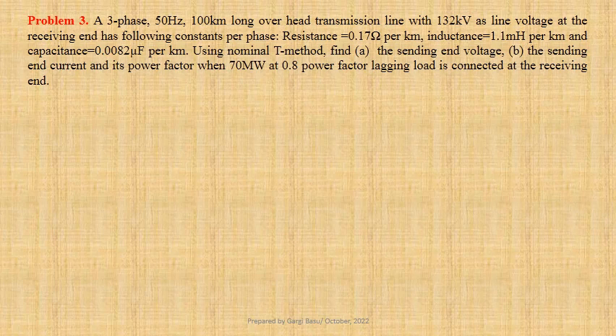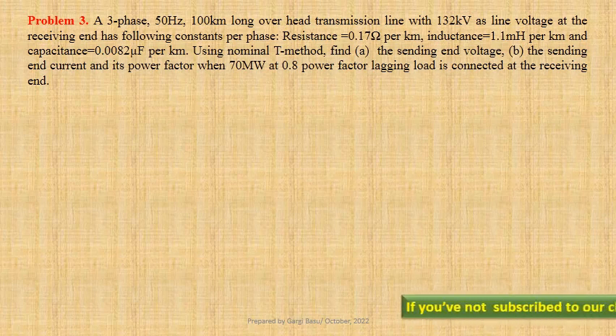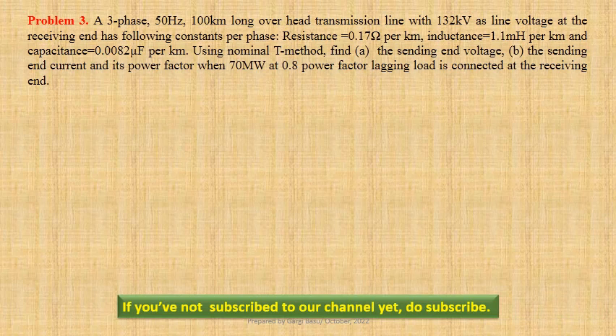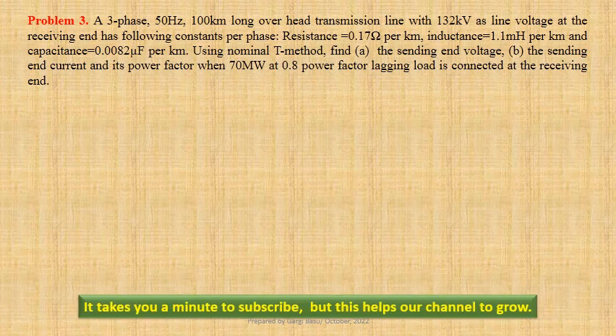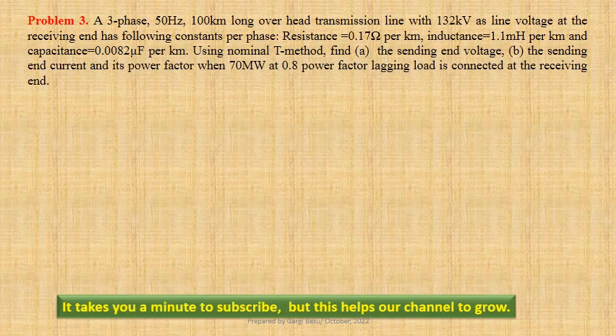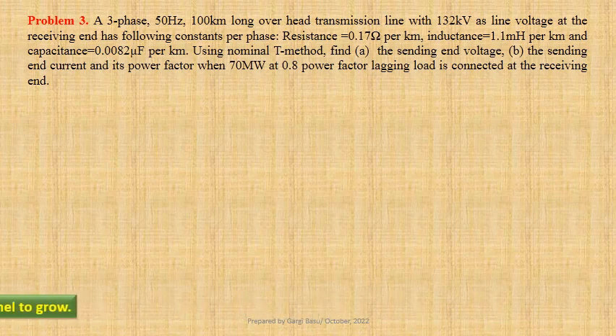A three-phase 50-hertz 100-kilometer long overhead transmission line with 132 kilovolts as line voltage at the receiving end has the following constants per phase: resistance equals 0.17 ohm per kilometer, inductance equals 1.1 mH per kilometer, and capacitance equals 0.0082 microfarad per kilometer. Using the nominal T-method, we have to determine the sending-end voltage, sending-end current, and its power factor when 70 MW at 0.8 power factor lagging load is connected at the receiving end.